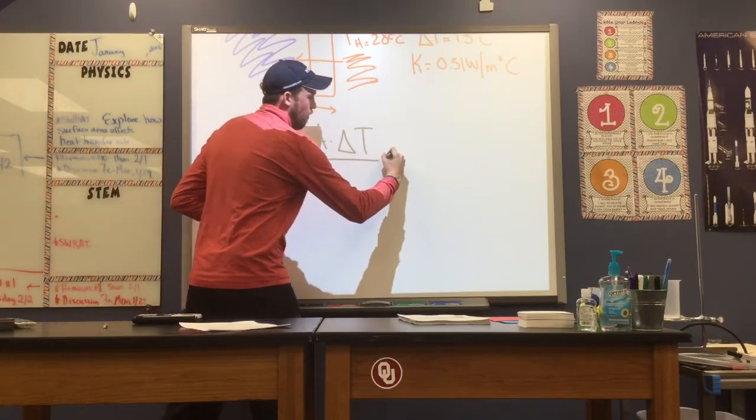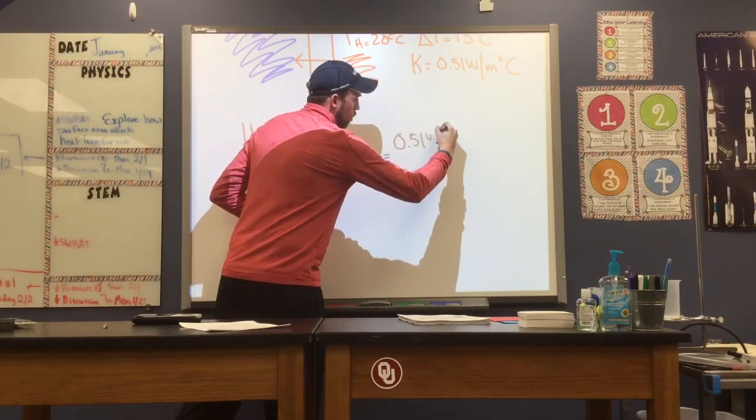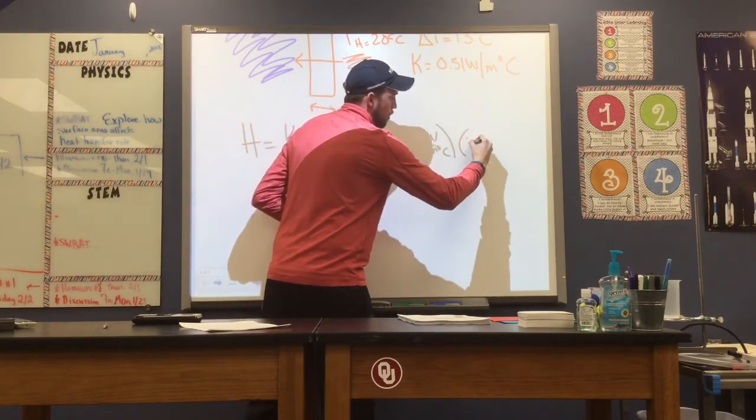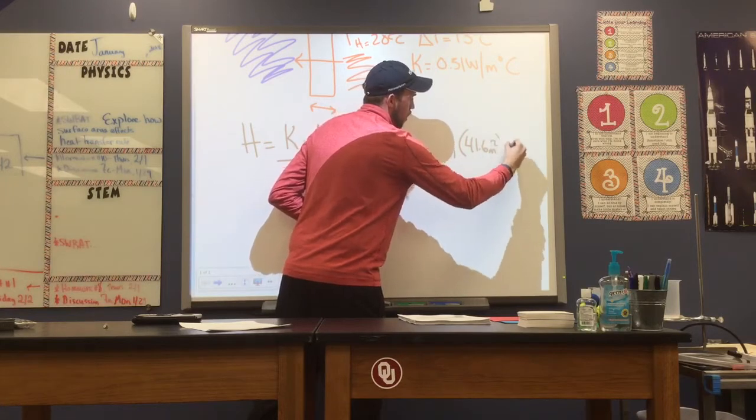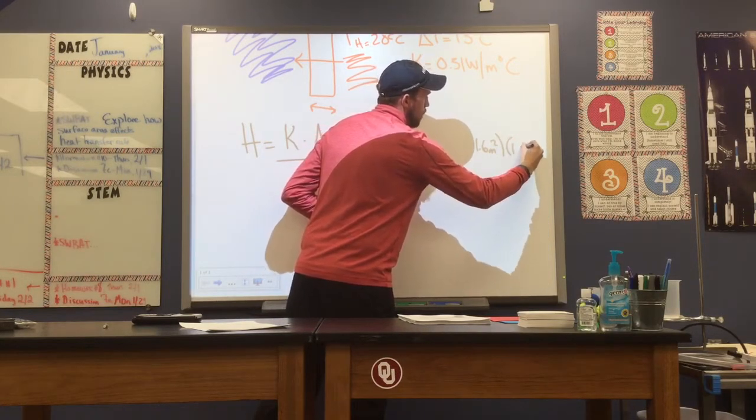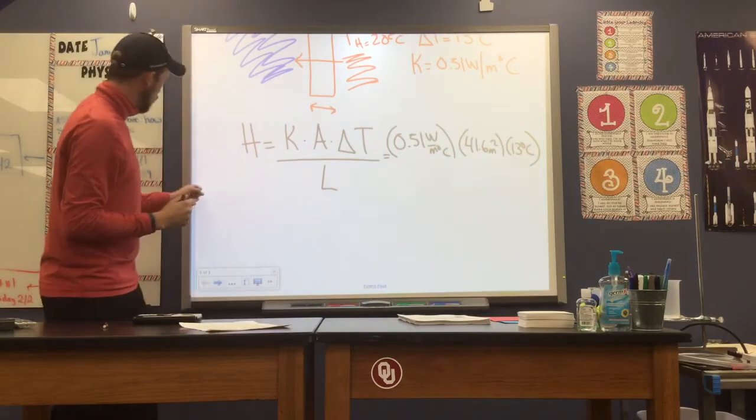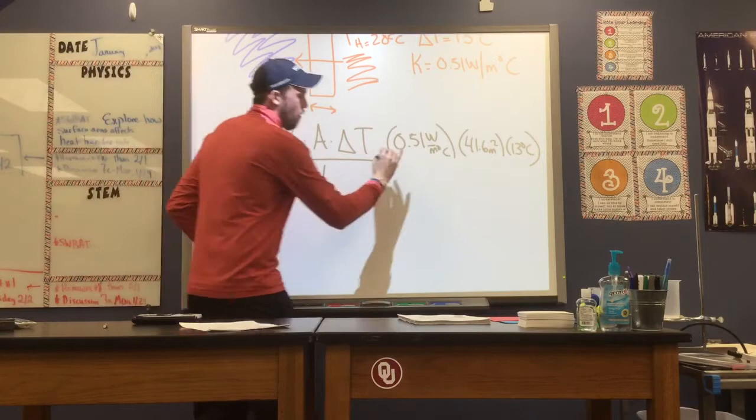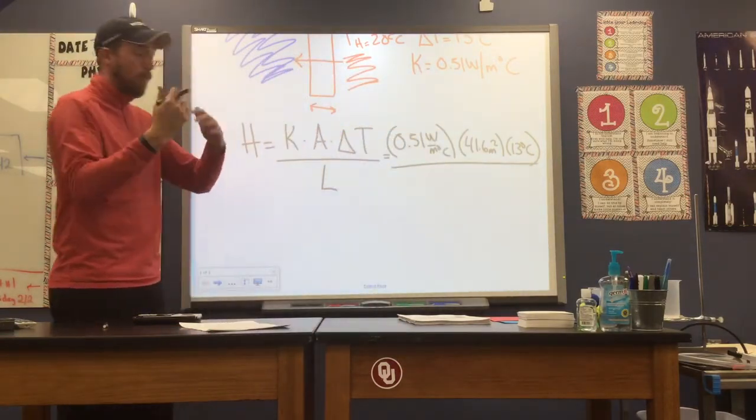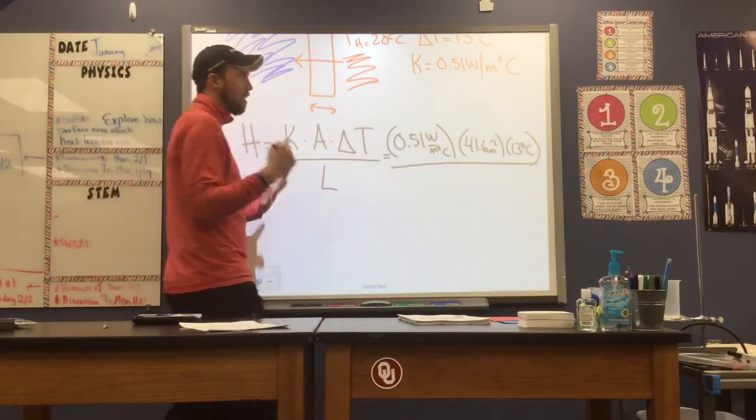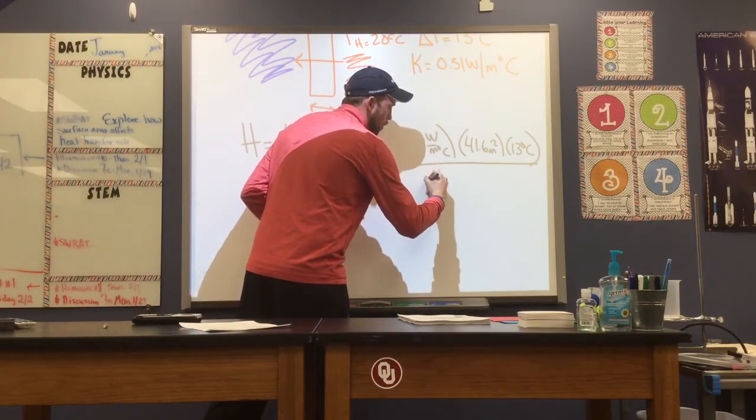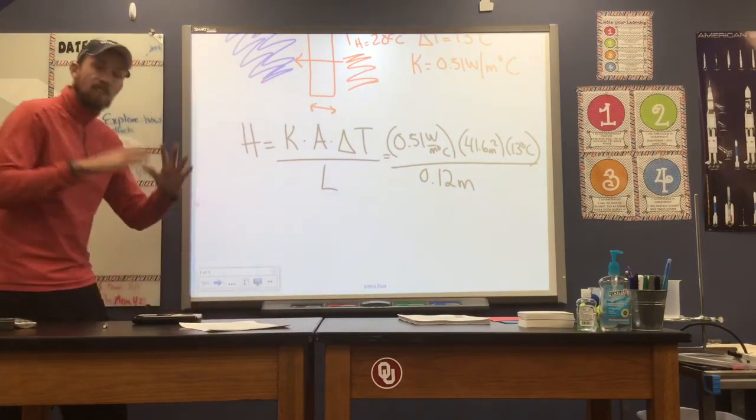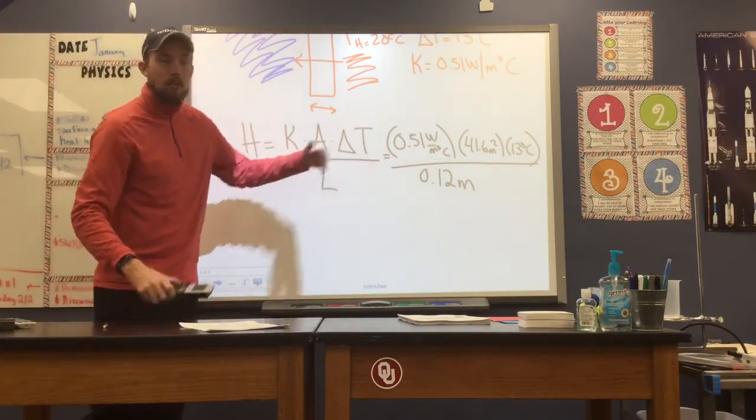So our thermal conductivity, 0.51 watts per meter degree Celsius. Our contact area, we just determined 41.6 meters squared, and our temperature difference was 13 degrees Celsius. Did I say that correctly? Yes, 20 and 7. Okay, so those are our variables in the numerator. And we'll divide by the length that our heat's passing through our thickness, which was 12 centimeters or 0.12 meters. So we've identified all of our variables. Let's go ahead and plug these values in and see what we come up with.